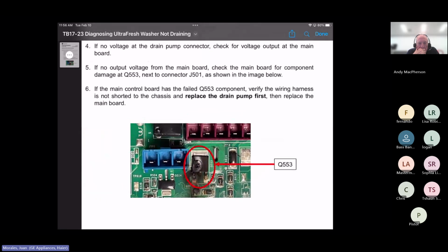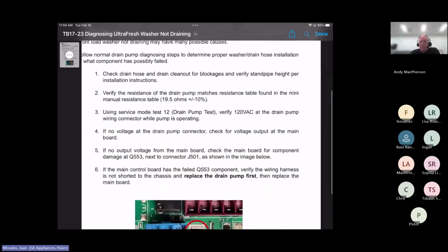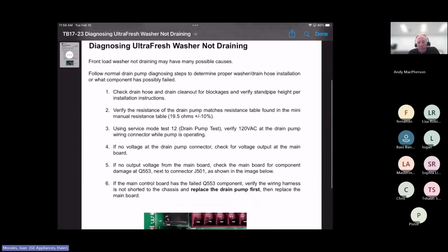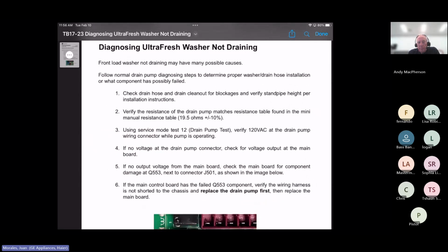So what it's telling you here, and I won't bore you with the reading unless you want to take a screenshot, is essentially to run test number 12, which is a drain pump test, to verify that you have 120 volts AC. It's also telling you, in step number 2 -- I went backwards here -- to check the resistance of the drain pump, which is 19.5 ohms.